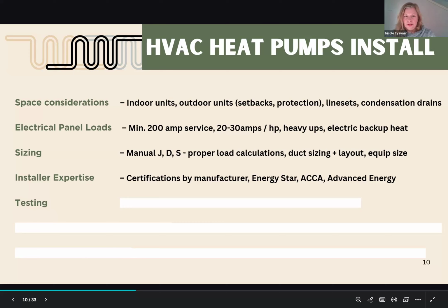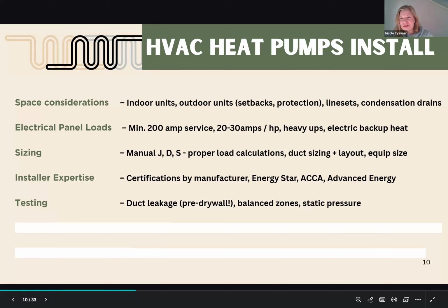Testing is very important. I'd make sure that's part of your scope of work - testing pre-drywall for the ducts, right before they seal up the walls, so you know if there are any problems and can address them. Also testing to make sure the rooms are well balanced, and static pressure testing on the equipment as well.